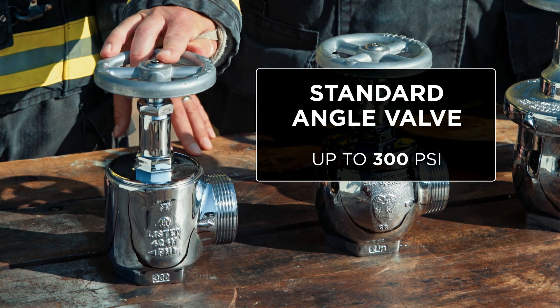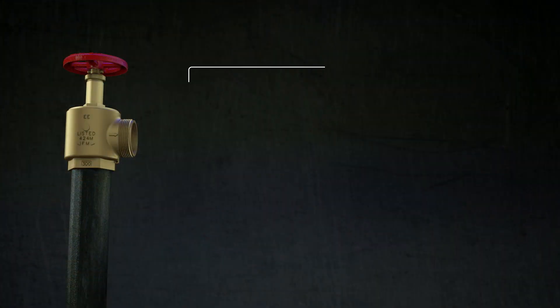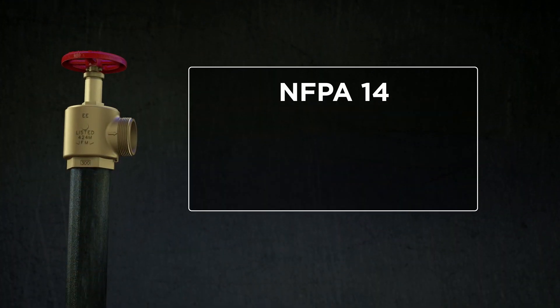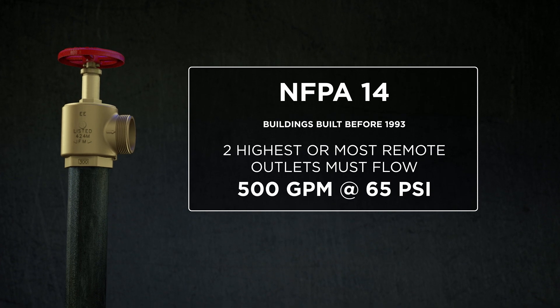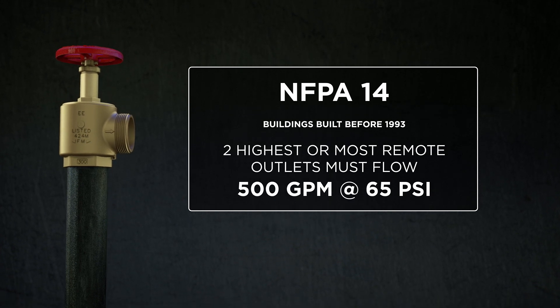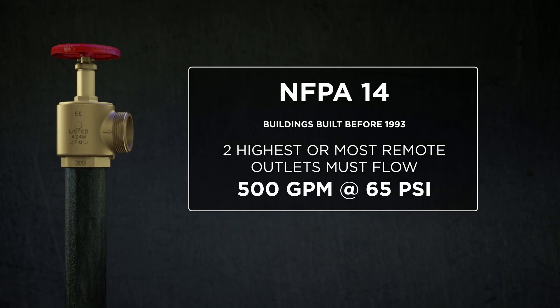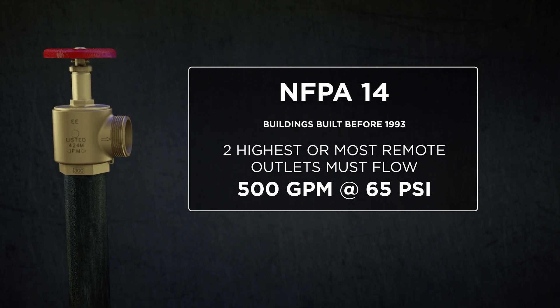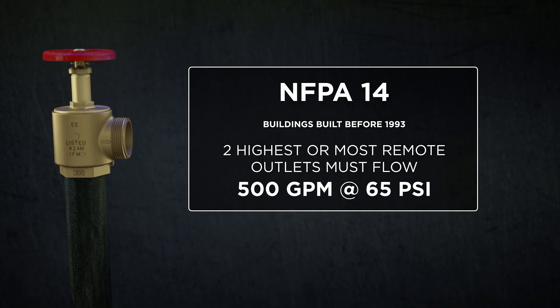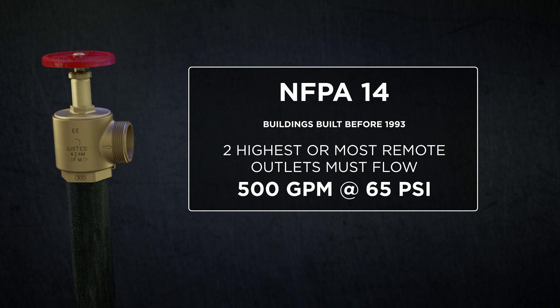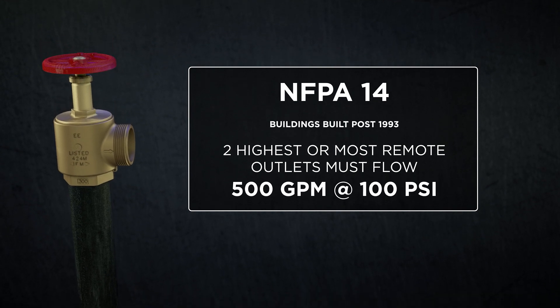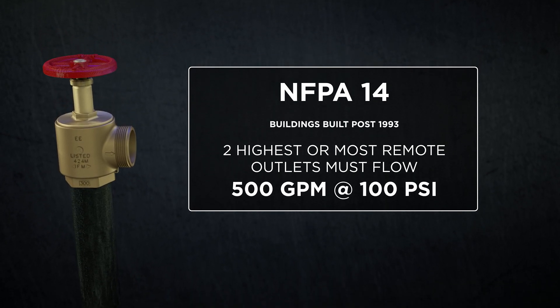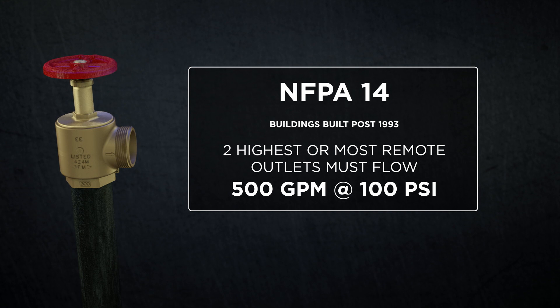Fire code requirements for pressure and flow for standpipe hose valve outlets is driven by NFPA 14. NFPA 14 states that the top two outlets, or most remote outlets in a building, must flow 500 GPM at 65 PSI for buildings built prior to 1993. Buildings built post-1993, the requirement is 100 PSI residual pressure for the topmost or most remote outlets flowing 500 GPM.